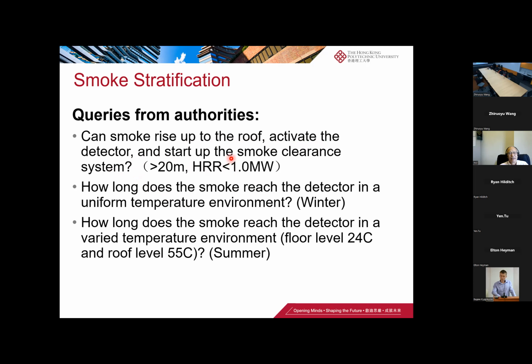This is Hong Kong Airport Terminal 1, and I think Terminal 2 and Terminal 3 are the same. This is not about the smoke control system, because the smoke control system is based on the design fire size, the heat release rate, to calculate the smoke production rate and then specify the extraction system and the capacity of the fan.